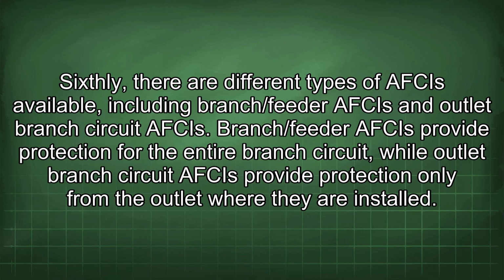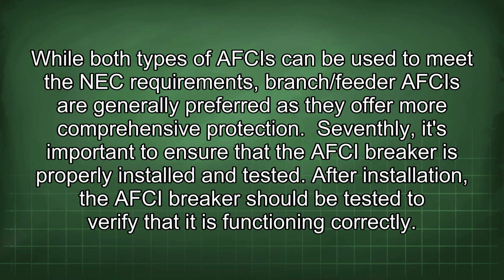Sixthly, there are different types of AFCIs available, including branch/feeder AFCIs and outlet branch circuit AFCIs. Branch/feeder AFCIs provide protection for the entire branch circuit, while outlet branch circuit AFCIs provide protection only from the outlet where they are installed. While both types of AFCIs can be used to meet the NEC requirements, branch/feeder AFCIs are generally preferred as they offer more comprehensive protection.